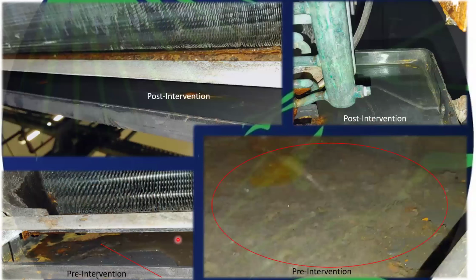Why? Because drain pans are hard to get to, and they are really tough to treat, especially with chemical treatment or chemical cleaning or recoiling. Everything drops into the drain pan. There's always this thin layer of water that's always going to be there, right? So if you're bringing all the bacteria, viruses, and contaminants from the coil into the drain pan, some of it will leave through the drain holes, contaminating everything in its way, and some of it will stay there, and then it's going to reproduce and retake the coil.